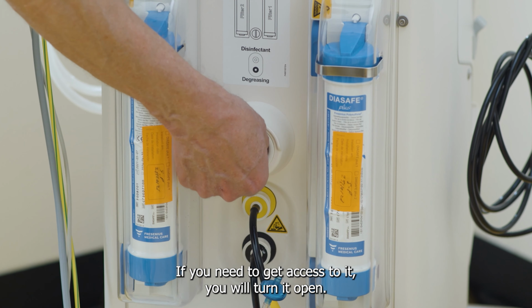To this side of the machine, these points here, that point there, allows you to open the arterial pressure measuring dome holder manually. If it doesn't open electrically, you can put a syringe on there and use physical force to push the holder open.